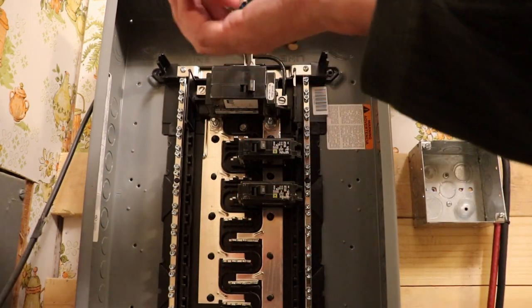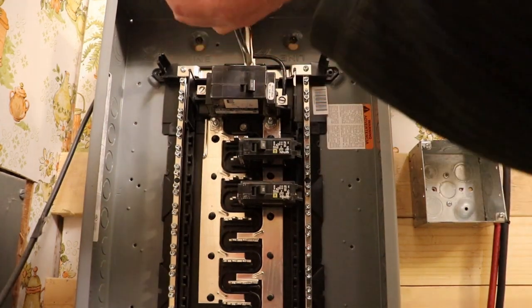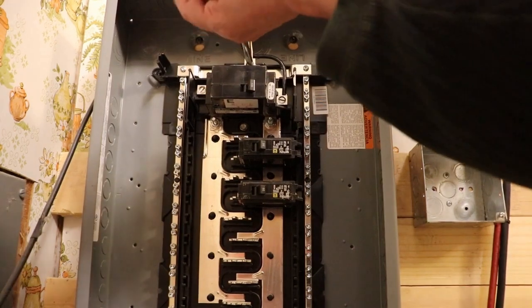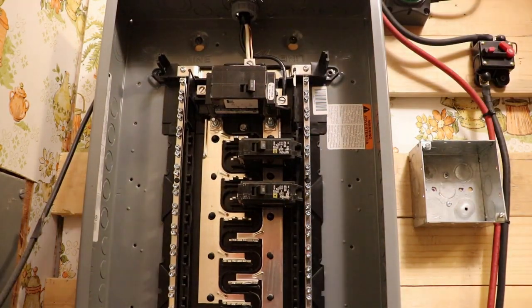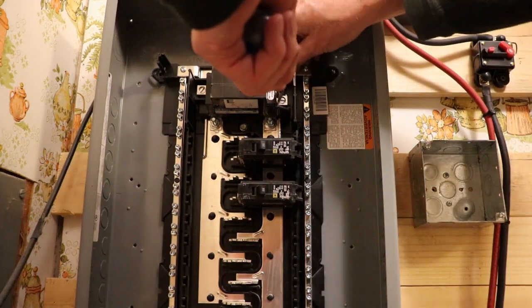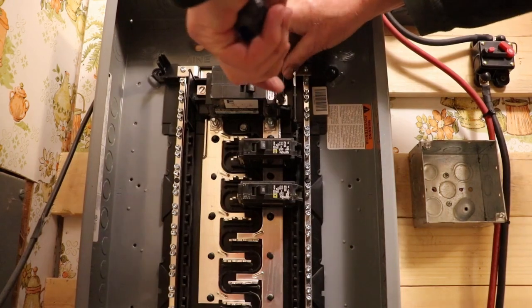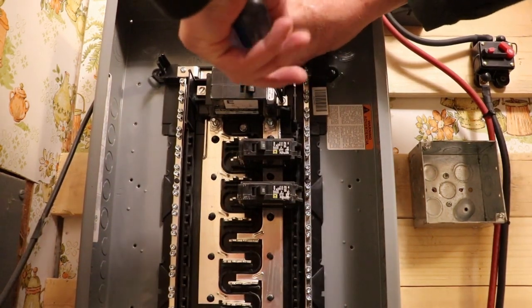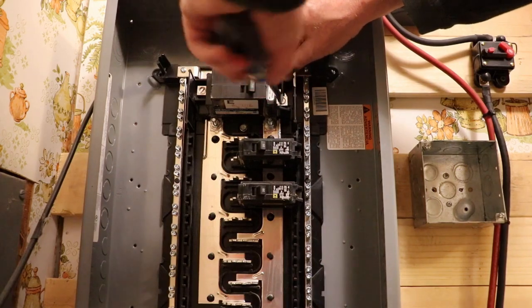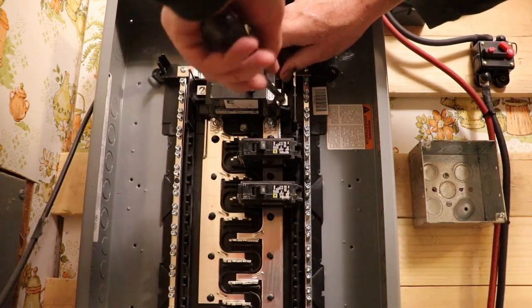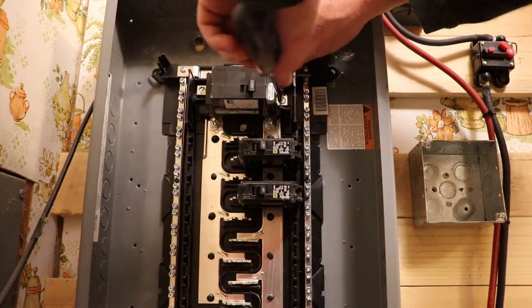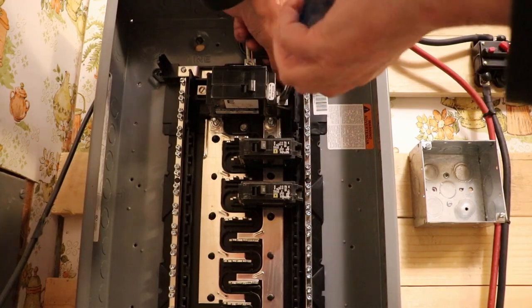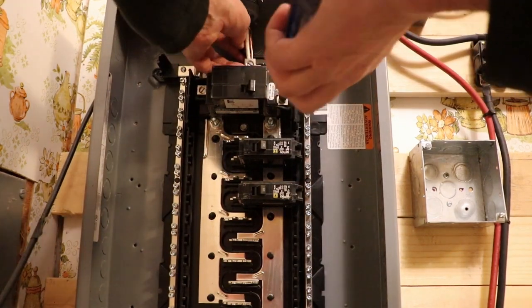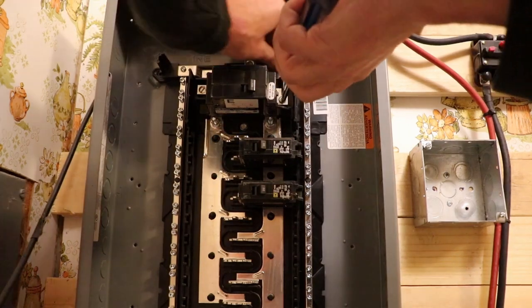Now I want to say one thing - let's talk about wire sizes and amperage for AC voltage. 12 gauge wire is good for up to 20 amps, 10 gauge for 30 amps, 8 gauge is good for 40, and 6 gauge is good for 55. Keep that in mind when doing this kind of work - the wiring requirements. I'll show you a chart later on where that's at. I know I've done it in another video, but you really need to pay attention to this, because if you don't, the wires could burn and your house could burn down, or wherever you're putting this could burn down, and you'll be out of luck.